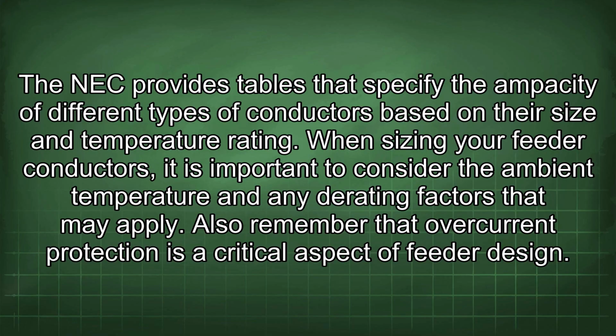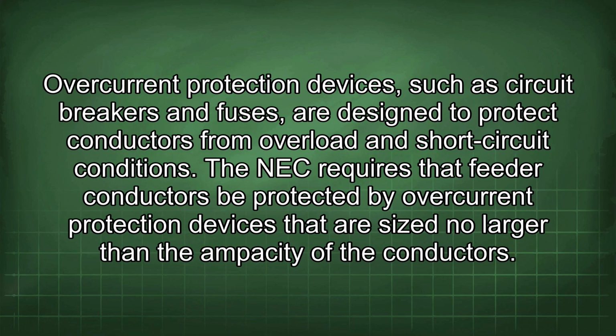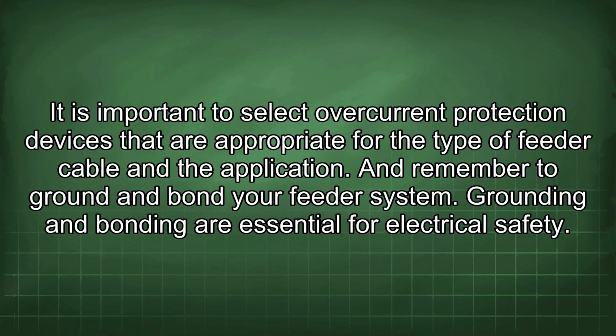Also remember that overcurrent protection is a critical aspect of feeder design. Overcurrent protection devices, such as circuit breakers and fuses, are designed to protect conductors from overload and short-circuit conditions. The NEC requires that feeder conductors be protected by overcurrent protection devices that are sized no larger than the ampacity of the conductors. It is important to select overcurrent protection devices that are appropriate for the type of feeder cable and the application. And remember to ground and bond your feeder system.